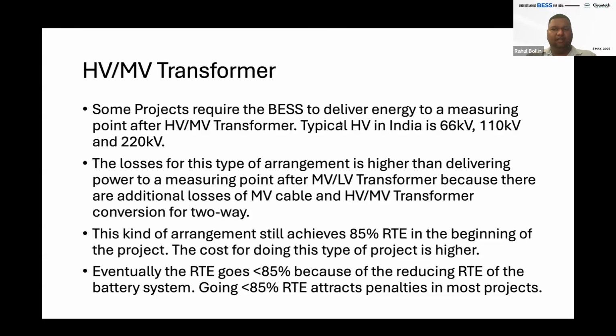I've seen some projects in India asking for this kind of setup. Keep in mind such projects need this extra transformer, and the cost goes up, since you have extra MV cables after the MV/LV transformer, plus this additional transformer. So the bidding prices cannot be apple to apple if this is included — this could be slightly higher. Also, this kind of project is very close to 85% RTE, versus another project where the measuring point is after MV, at an MV point.